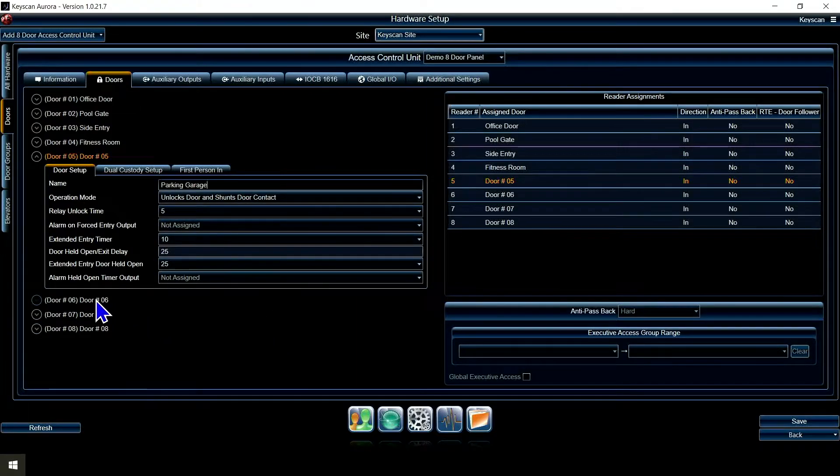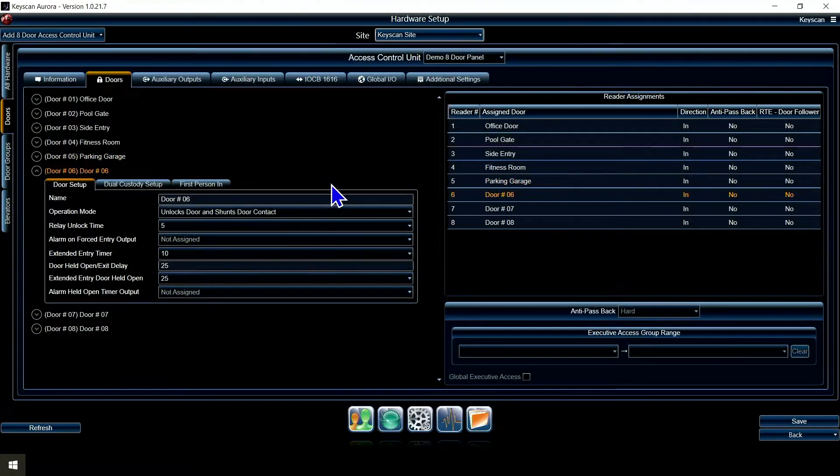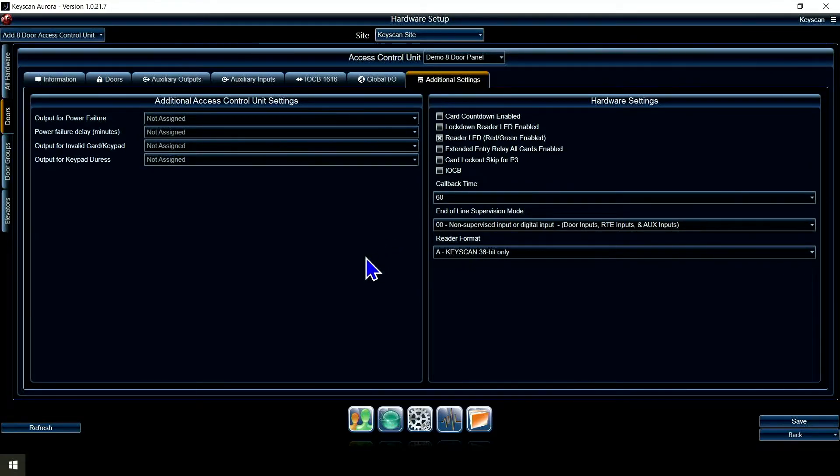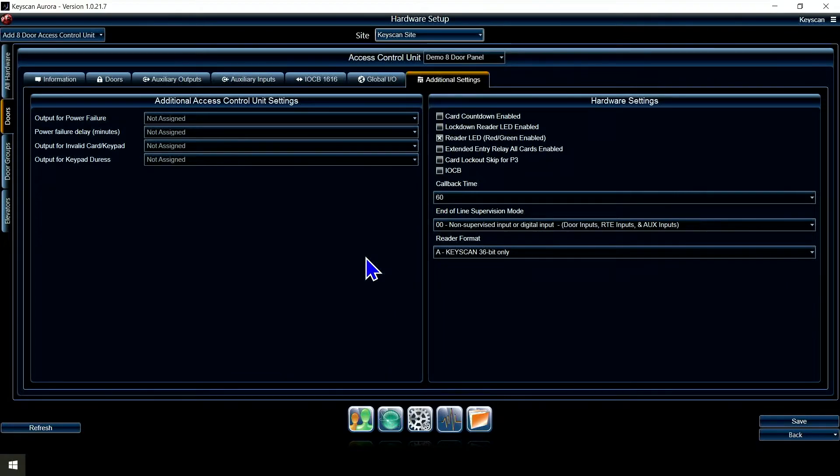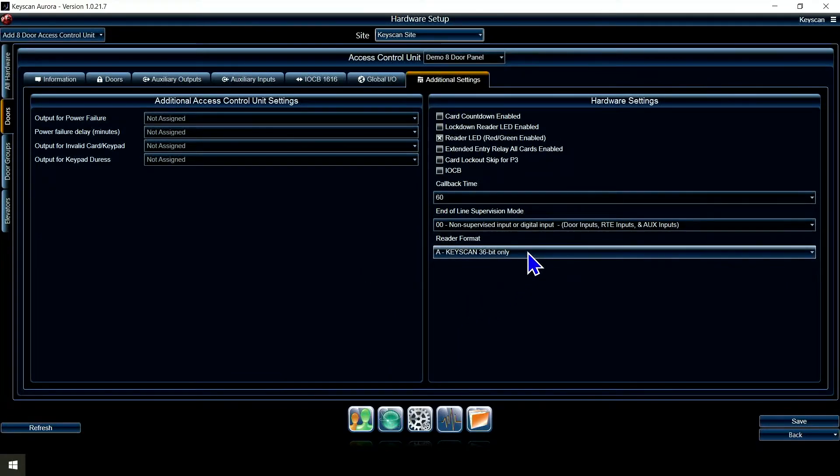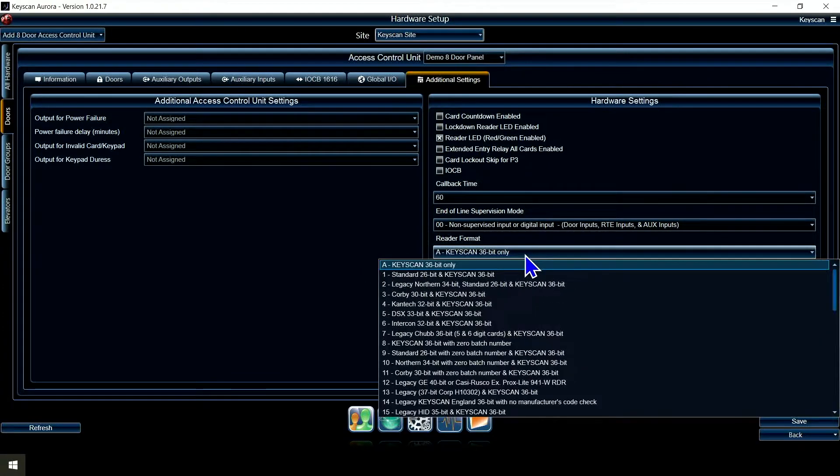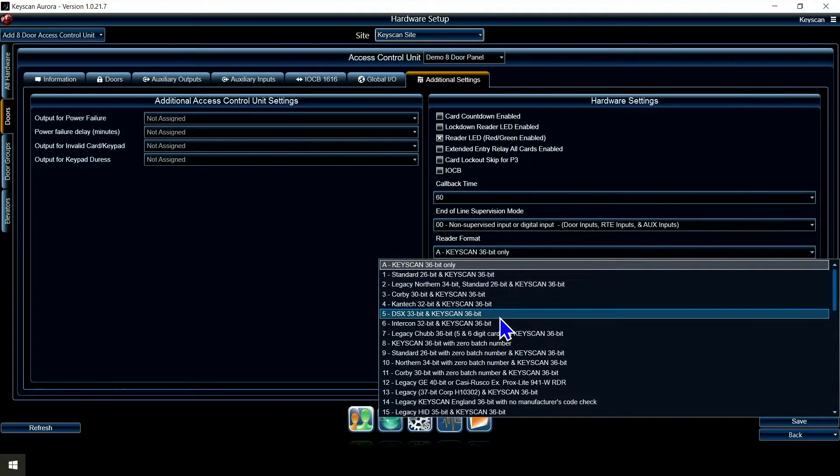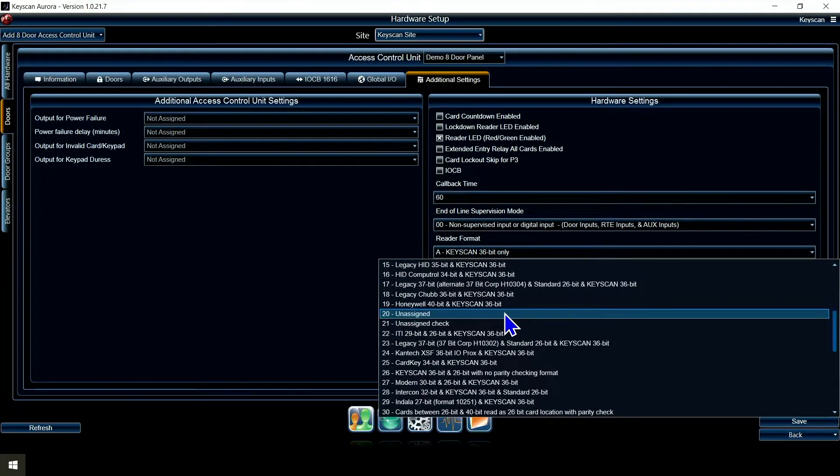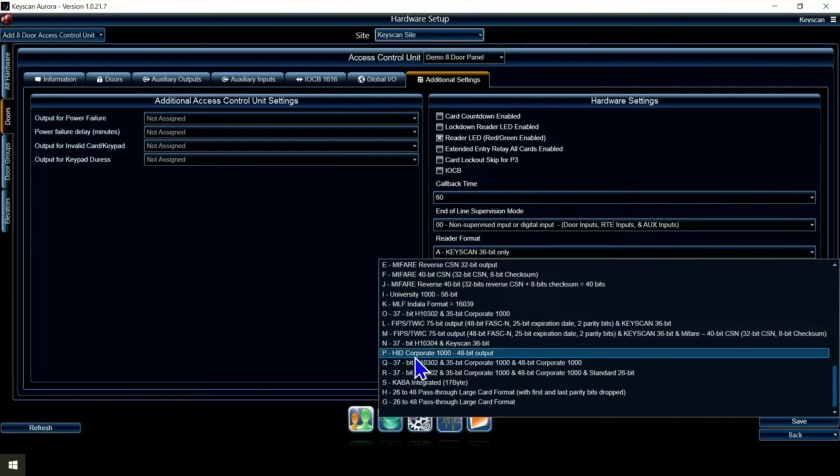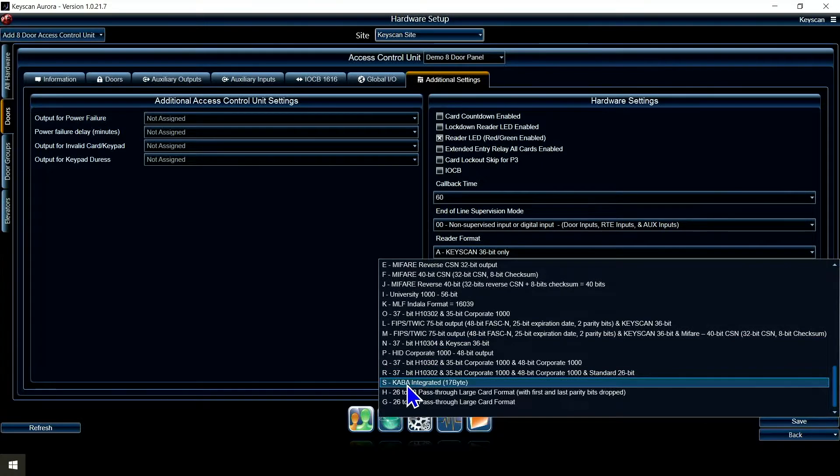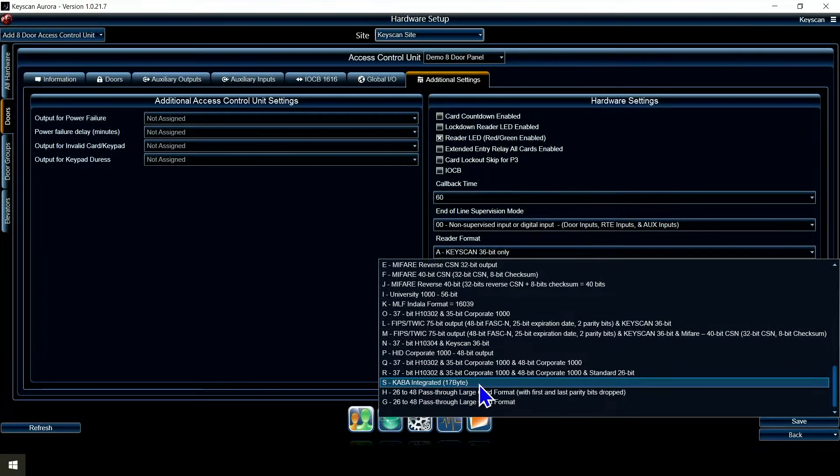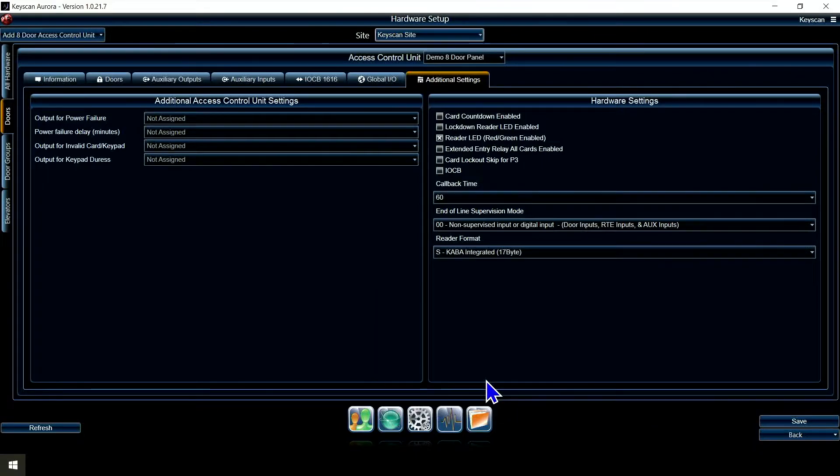You can put whatever your doors are, you can label them here. Now if I go to additional settings, there's one thing that's here that's not on that CA-150 panel: we've got to set our reader format. That's the big thing. Reader format by default is set to key scan 36-bit, but for this integration with Kaba I've got to scroll all the way down this list to option S, as in Sam, for Kaba integrated 17-byte.